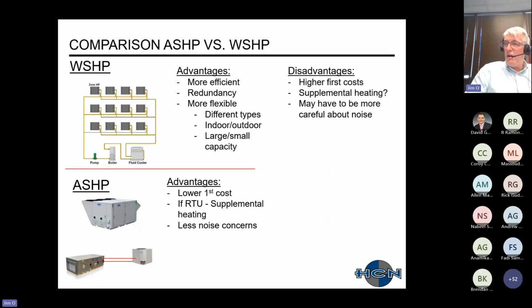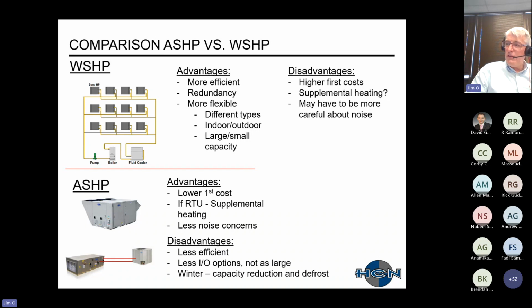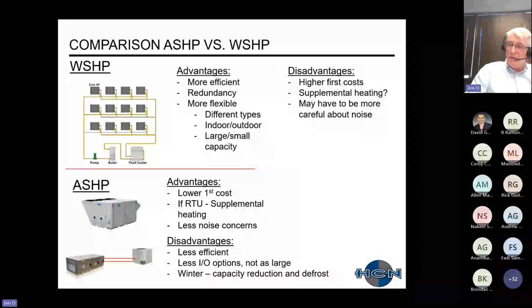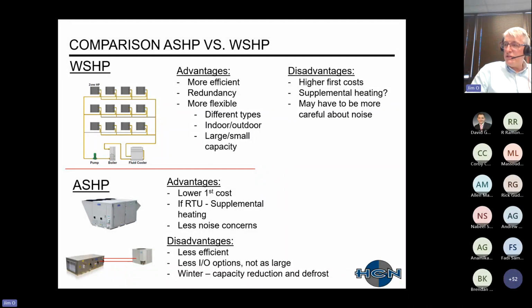Air source heat pumps are lower first cost overall. You don't have to run all the piping around, et cetera. If it's a rooftop unit, it's very easy to add supplemental heating. There's obviously much less concern about noise because these are typically in remote locations. Disadvantages: you have fewer options for indoor-outdoor units. They can't be as large. And then obviously, as we talked about, in the wintertime you have to be cognizant that you will have a capacity reduction, and you do have to plan for defrost mode.